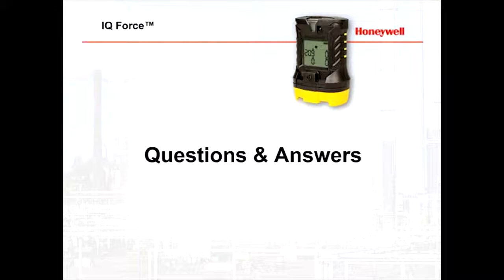Yeah, absolutely. When we specify the lower temperature spec, that means we've tested everything that needs to work at that temperature. We usually go well below the lower spec to make sure everything that comes out of our factories works. So when we spec it at minus 18 Celsius, we've tested down to minus 30 Celsius, and we make sure the LCD works, the alarms work, the data logging works, it survives being dropped at that temperature, and the buzzers, sensors, and pump all work, with no false alarms at those temperatures.